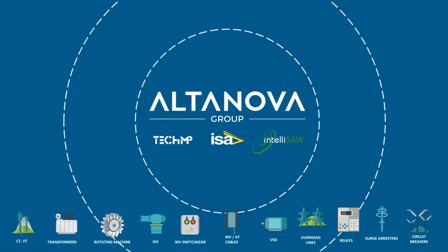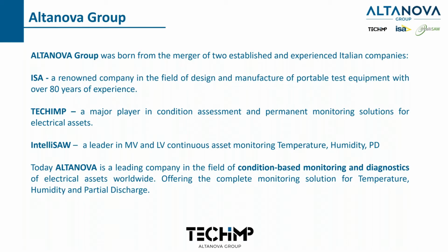We're part of Altanova Group, which basically consists of three companies. ISA, who's been around for 80 years, and they manufacture portable test equipment, circuit breaker testing equipment, tan delta, and such. And then there's Techimp, which is what we're going to be talking about today, who specifically is a global leader in both partial discharge testing and monitoring solutions of all electrical assets, not just cable. And then IntelliSAW, who's also a leader in medium and low voltage monitoring for temperature, humidity, and also partial discharge in medium voltage equipment up to 40 kV.